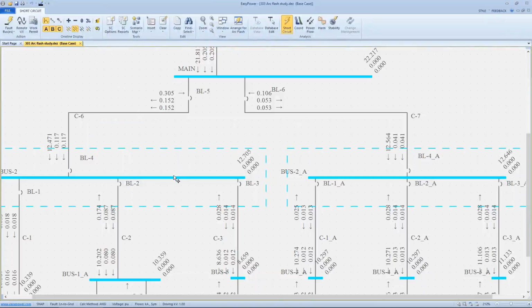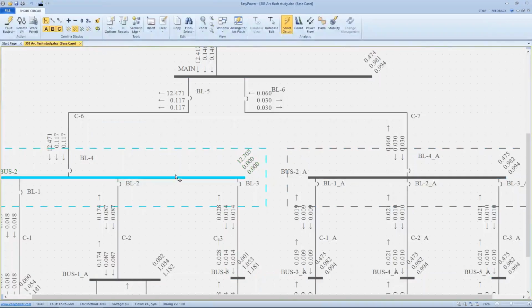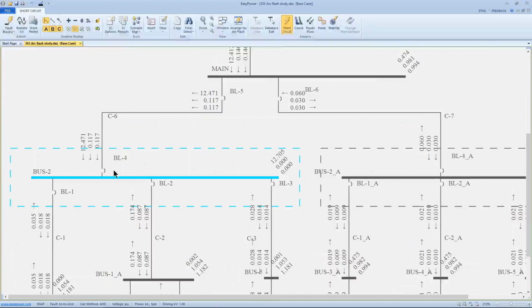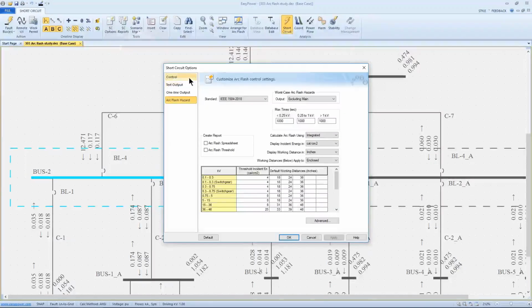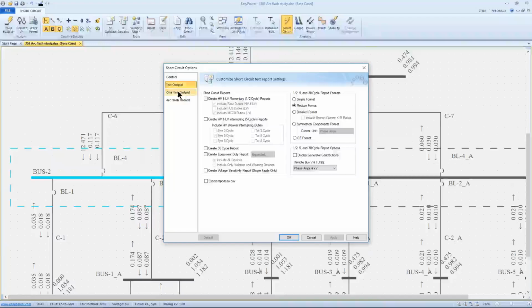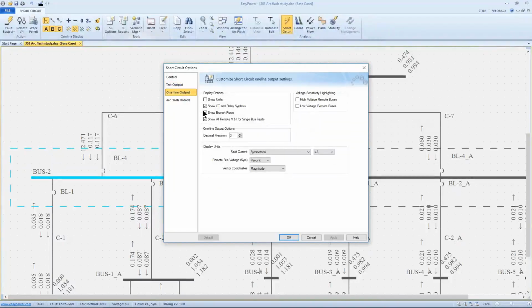And for those of you that don't use the tool that often, what we're displaying is a single bus fault. In this case, I've just highlighted bus 2, and so it's the faulted bus, and all this other data that we're showing would be considered remote current, and this is all a function of the way short circuit options allows us to display the one-line output. So in this case, we're showing symmetric current, we're showing remote bus faults, and magnitude only.